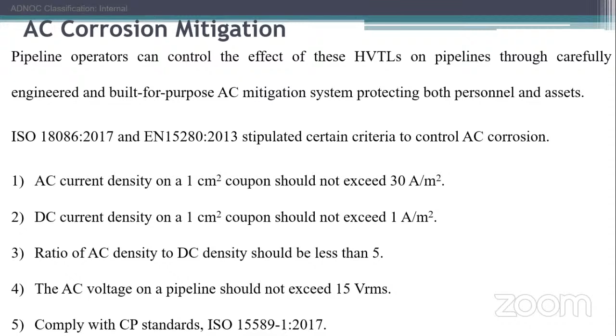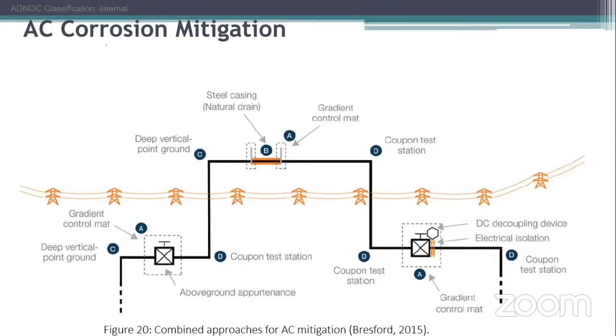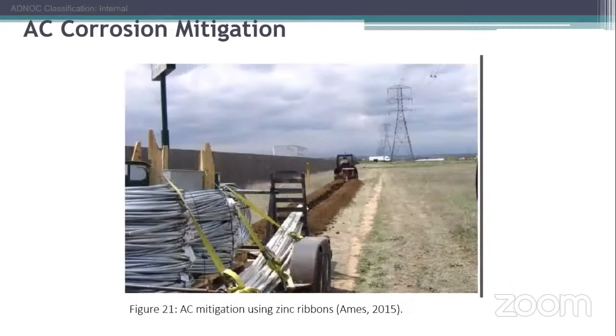To protect our pipelines from this form of corrosion, we can ground our pipelines and use DC decoupling equipment. DC decoupling prevents DC from grounding while allowing only AC to ground. The DC comes from the cathodic protection, because if we just ground the entire pipeline, both the cathodic protection and the AC will all go to ground. But we need our cathodic protection to protect the line.